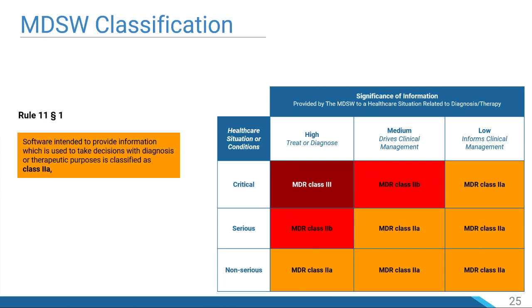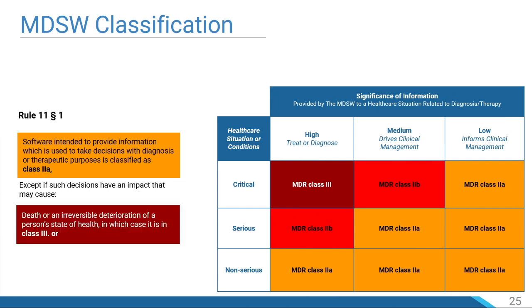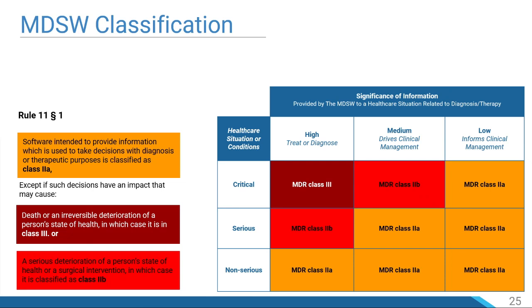You could say, okay, why isn't there a class 1 for software? Well, at the end, yes, all other software will be considered as class 1, but in real life for a medical device, class 1 is never applicable because you always have some kind of information processing. So it's always class 2A as a minimum, except if this decision has an impact that may cause, in the worst situation, death or irreversible deterioration of a person's state of health. In that case, it's class 3. And if this is a serious deterioration of a person's state of health or a surgical intervention, then in that case, it will be 2B.